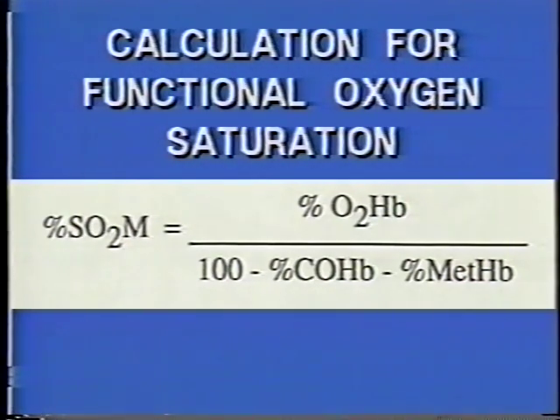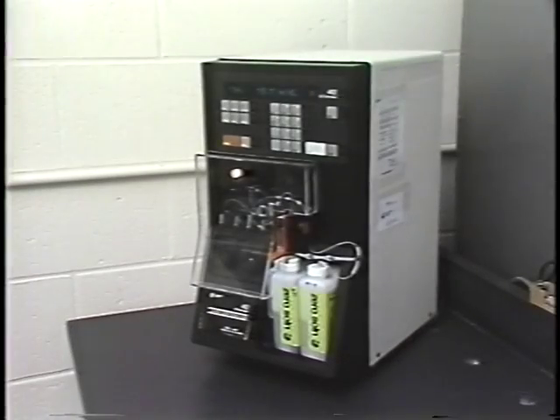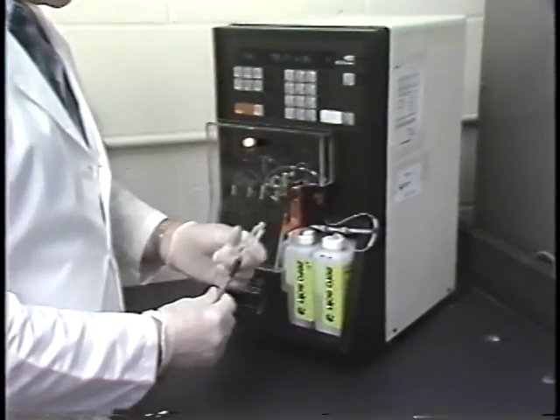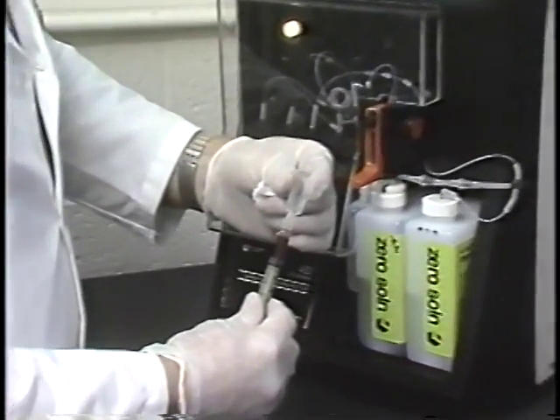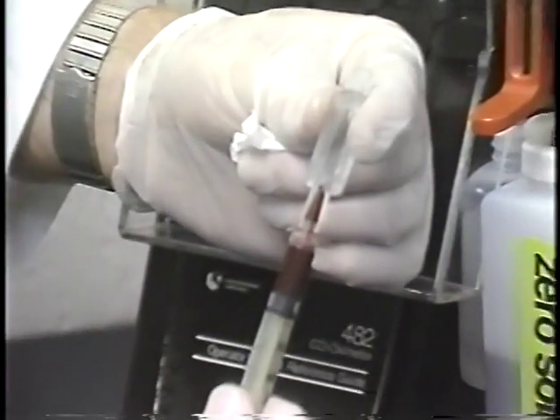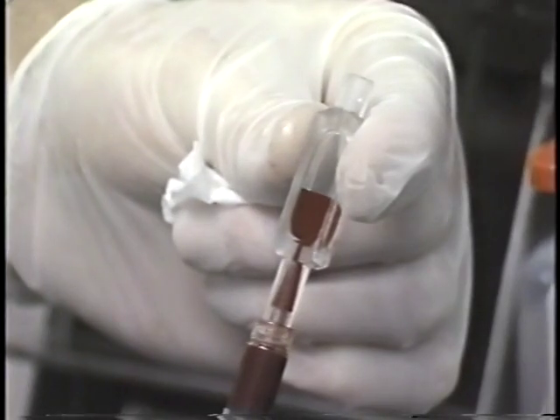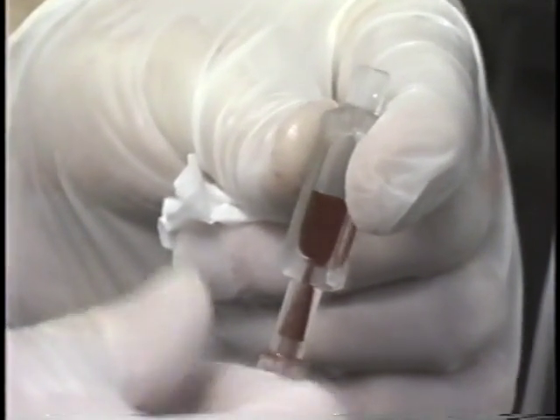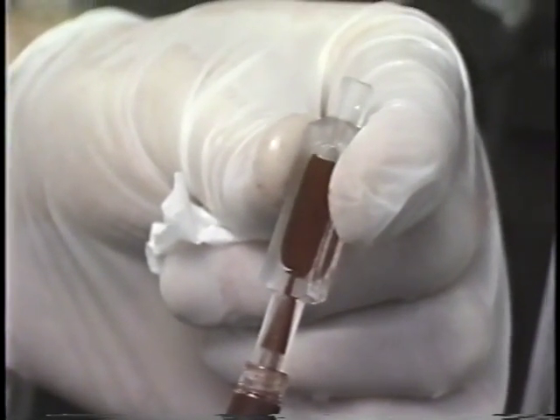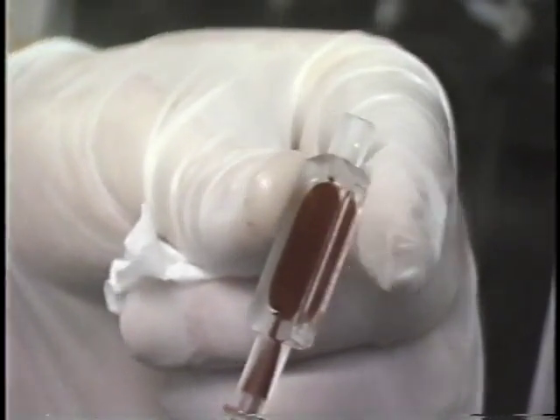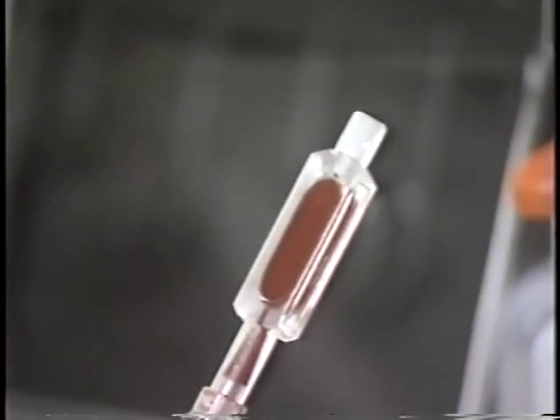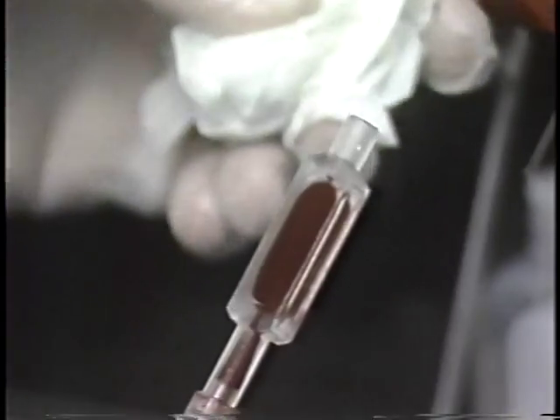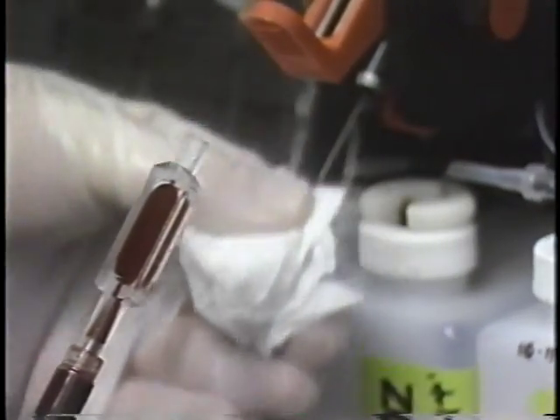All co-oximeters are very similar. For illustration purposes, we will use an IL 482. Inject the blood into the cuvette. Note that there is no plug in the end of the cuvette. Fill the cuvette to the base of the short neck. Wipe the sample probe first and sample from the cuvette directly.